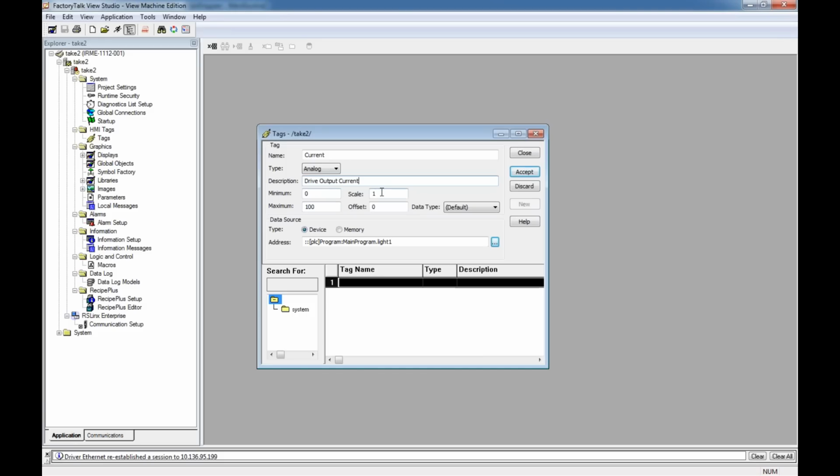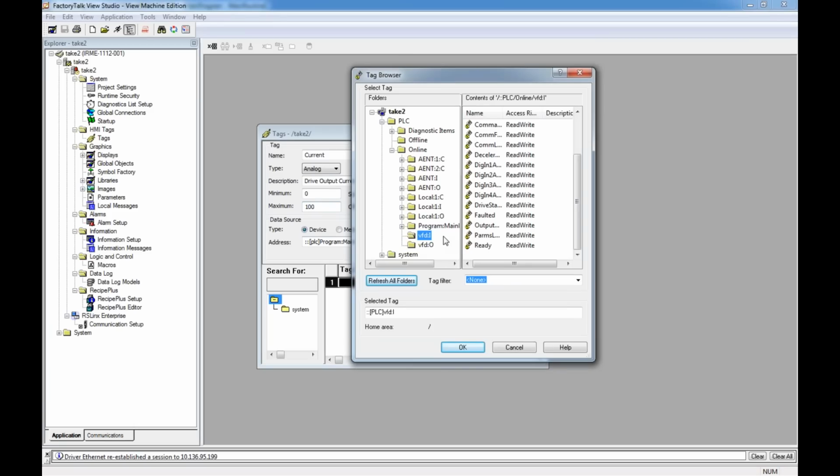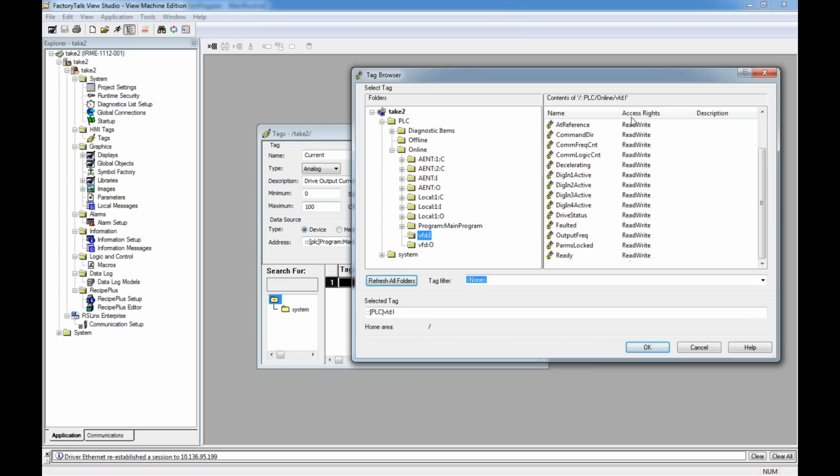Now I can have a minimum and I can have a scale, okay? So it may come in as 600, so I'm going to give it a scale 0.1 to move the decimal point over 1. And make it a minimum of 0 and a maximum of 60, just to play, okay?